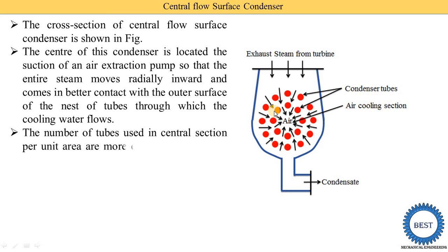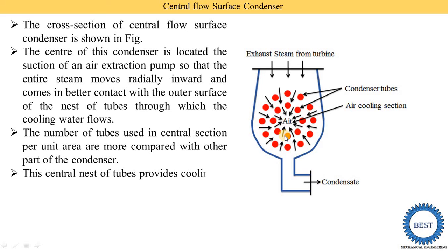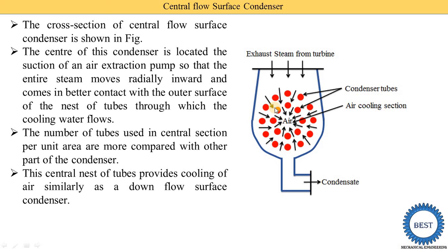The number of tubes per unit area in the central section are more compared with other parts of the condenser. At the center portion, there are more tubes compared to the other portions. This central nest of tubes provides the cooling of air similarly to a downflow surface condenser — better cooling of the air is carried out at the center, similar to downflow surface condensers.